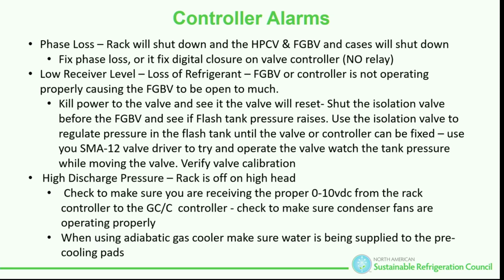We always want to start at the first alarm of that series. Not if I had one trip at 5 o'clock in the morning and now I'm at 10 o'clock in the afternoon. That doesn't count. But in that series of alarms, I want to be careful. All right, so phase loss. Like Brett said, it's going to shut us down and it's going to save us. Sometimes it's going to be a struggle to start back up if we don't trip properly. That's why on phase loss we have a UPS. So we have power; if it is a true phase loss, it should shut those down.